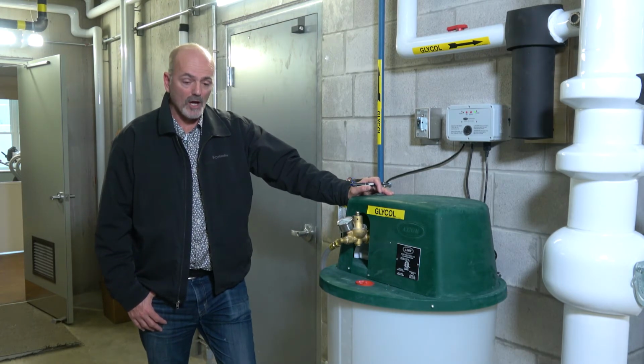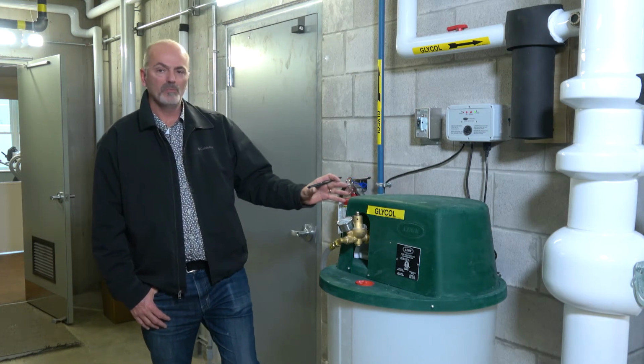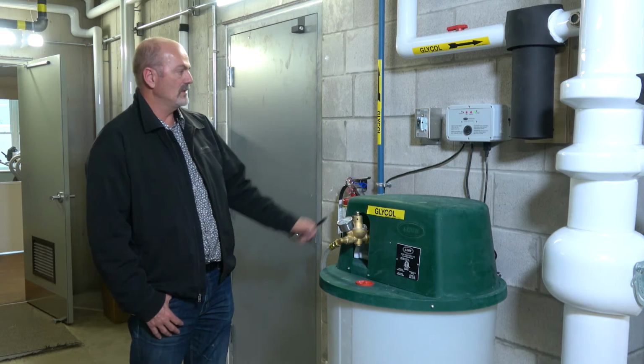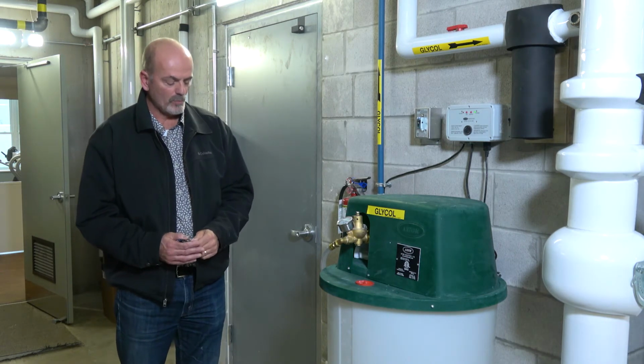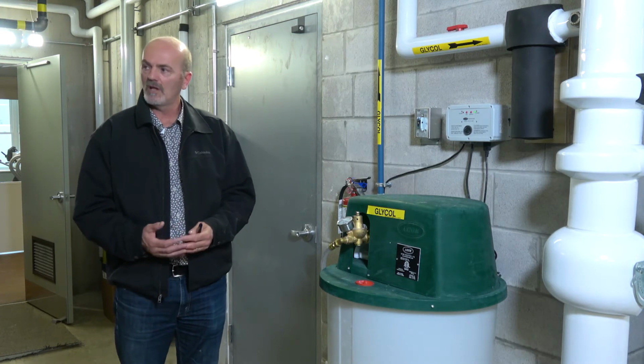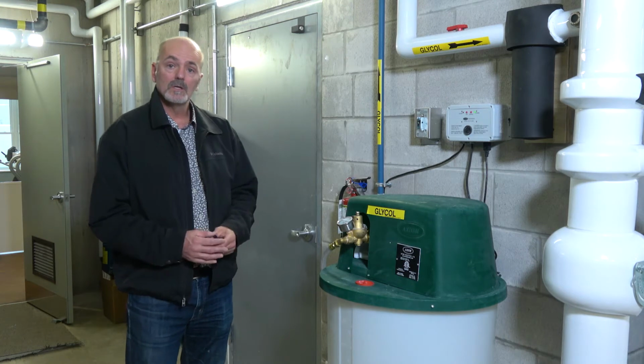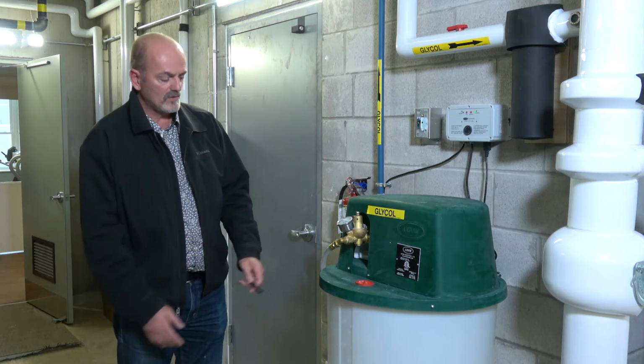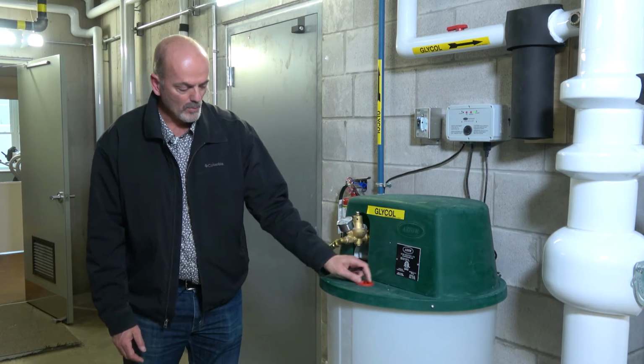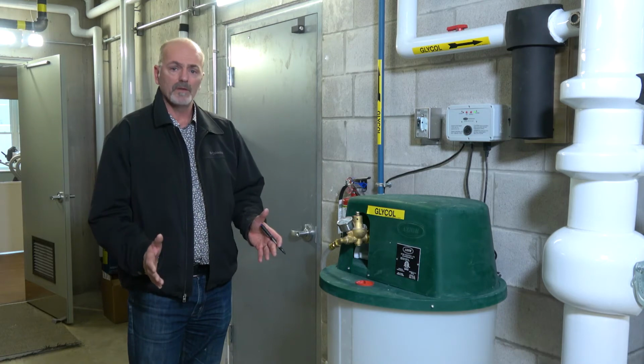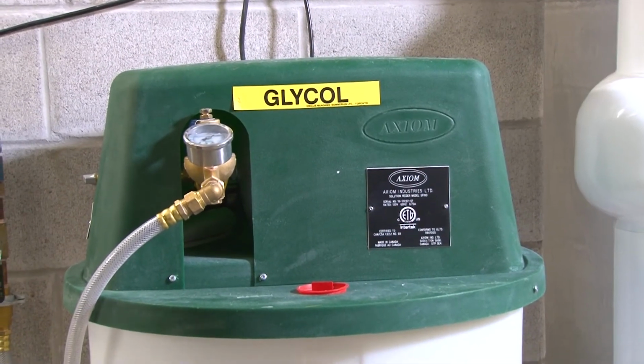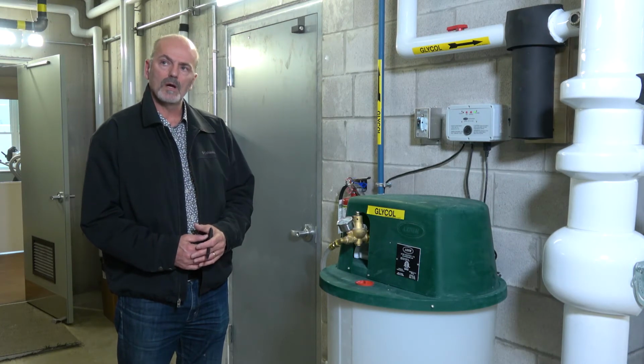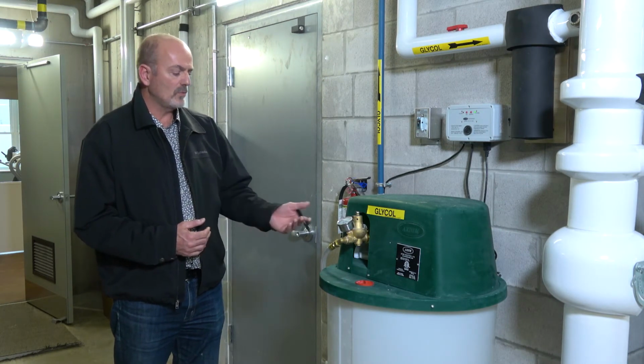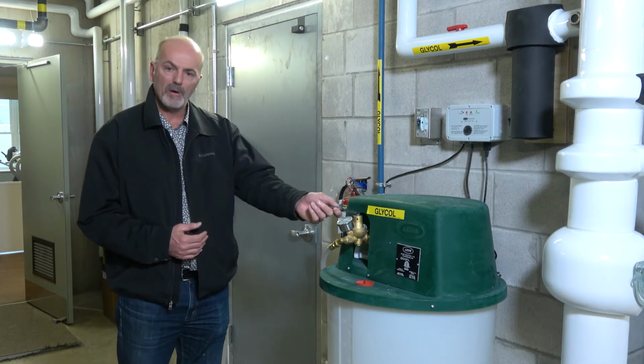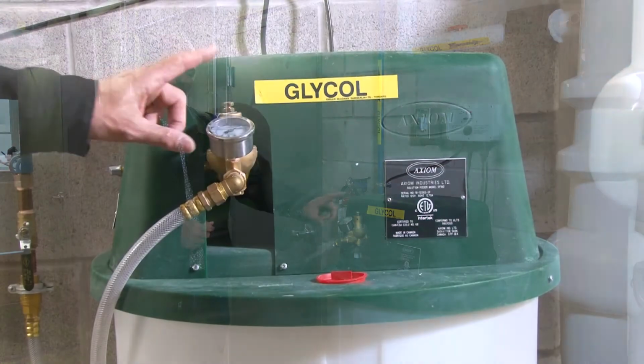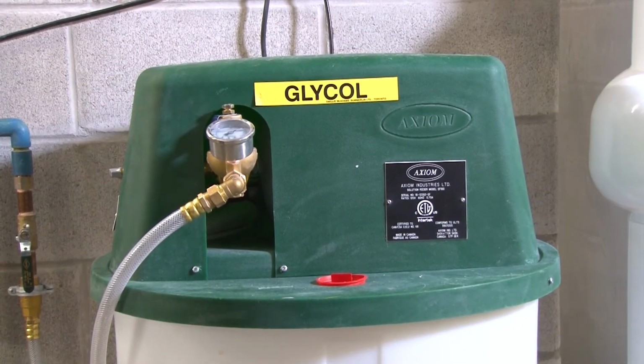Equipment we have here is a system/glycol feeder. It's automatic. How it works is there's a built-in pressure device in here that senses the pressure in the system. And what it's used for is when we have systems that have special fluids in them, such as glycol, where we want to maintain a mixture of water and glycol at a certain percentage, the tank gets filled through the fill port with pre-mixed glycol. In this case, it's probably either 40 or 50% glycol and water. So this way, if our system needs to have some fluid added to it, essentially this will sense the pressure drop, add the fluid because there's a pump in here, and pressurize the system back up to the design pressure that this valve is set at.